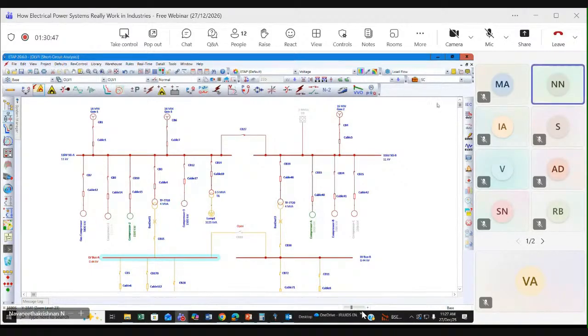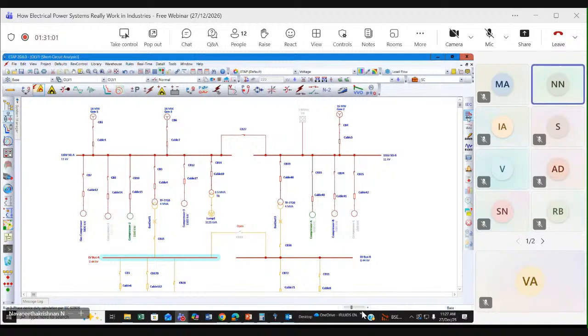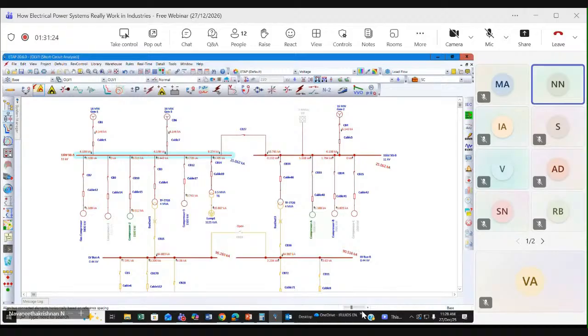Okay, I'll another few minutes is there. What time? 11:40. So another few minutes I'll run short circuit analysis here. Standard for this, and so you can see the generator is supplying 6.1 here. So this, if we see this bus, it is rated for say 108 kiloamps peak current. So peak bus is safe now. You can see here the fault current is only 6. You can see here 25 kiloamps.